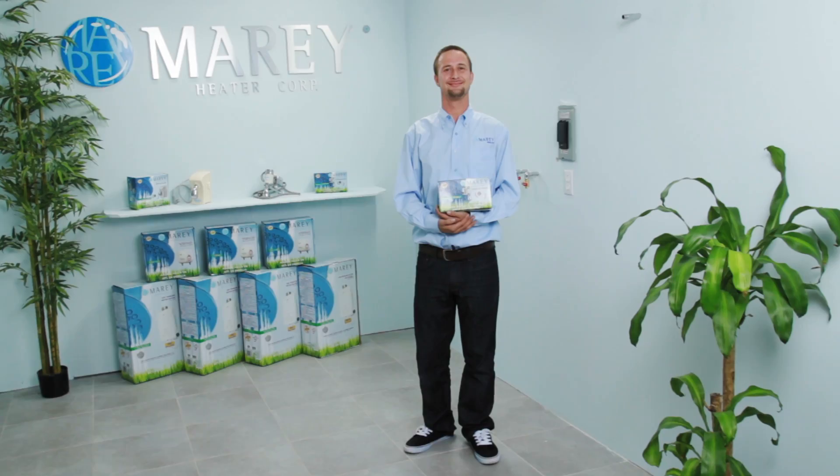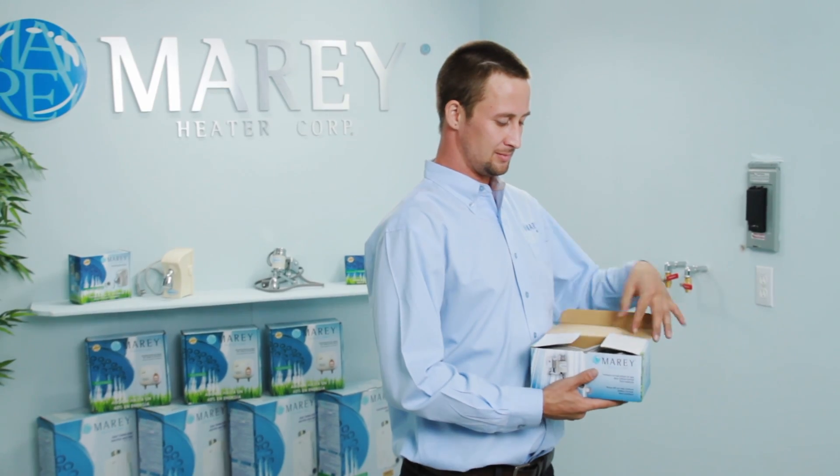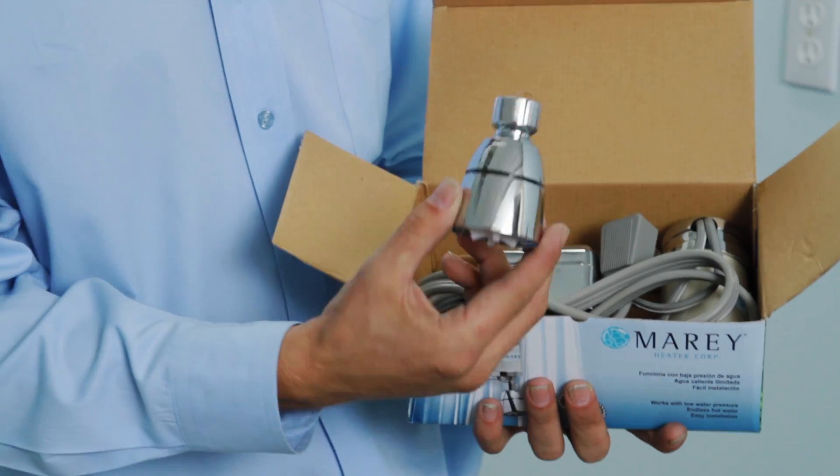The 110 volt version requires a 30 amp dedicated circuit for proper operation. The 220 volt version requires a 15 amp dedicated circuit. The circuit breaker should never be shared with any other electrical devices.